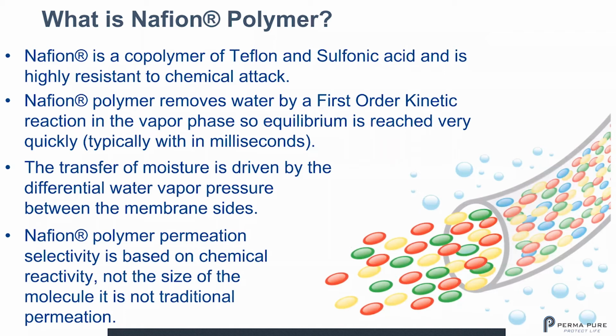So what is Nafion? Nafion is a copolymer of Teflon and sulfonic acid and is highly resistant to chemical attack. Nafion polymer removes water by a first-order kinetic reaction in the vapor phase, so equilibrium is reached very quickly, typically within milliseconds. The transfer of moisture is driven by the differential water vapor pressure between the membrane sides. And the Nafion polymer permeation selectivity is based on the chemical reactivity of water with the membrane. It's not traditional permeation, it's not based on size.